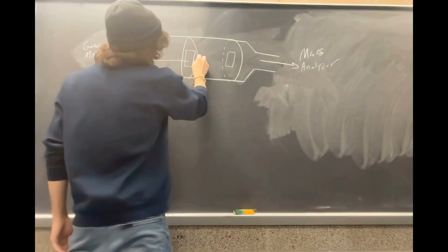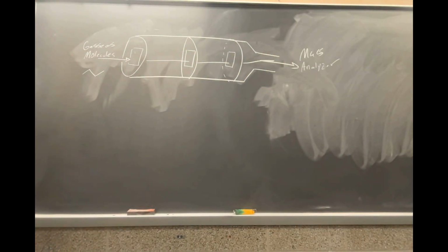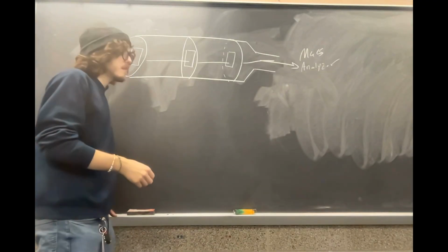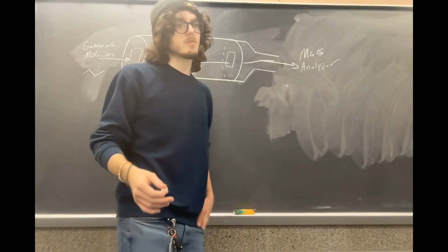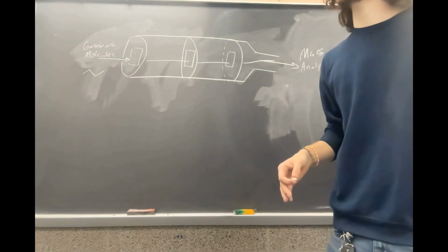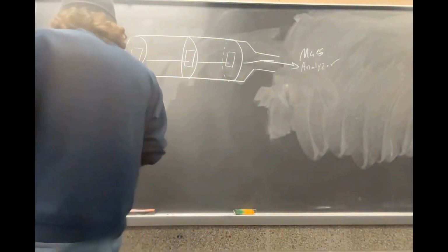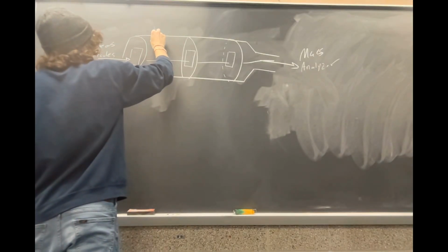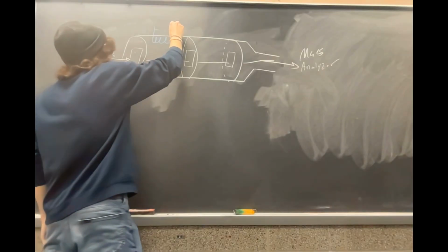So you have your gaseous molecules come in. They're going to pass through this thing that we'll discuss later, and then go to the mass analyzer. Hopefully you can follow that. It's not anything too difficult. But think about the name. This is an ionizer. We need to ionize these gaseous molecules coming in, and in fact, we also fragment the molecules when we do this. We have this little mechanism here, and these little curly things are usually a filament. Typically this is a tungsten filament.